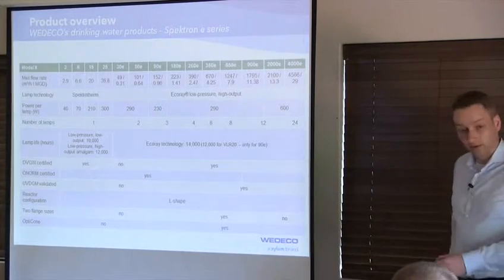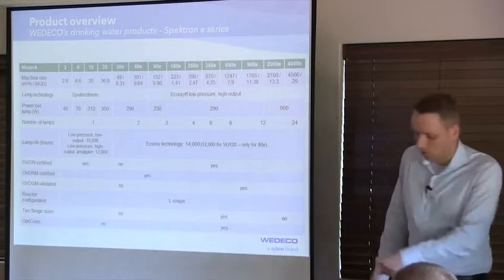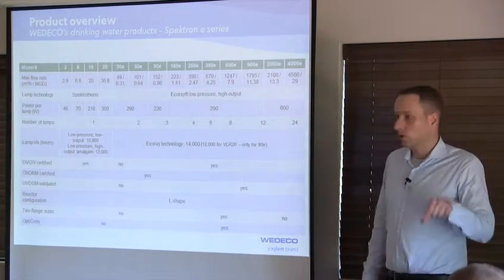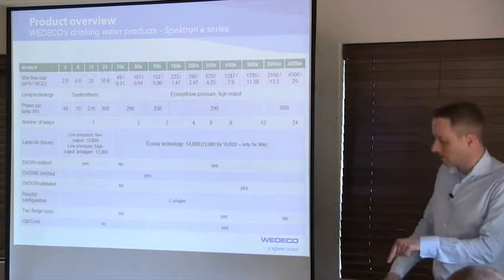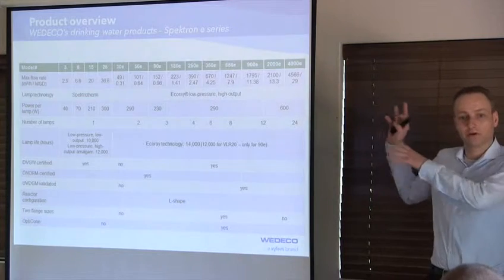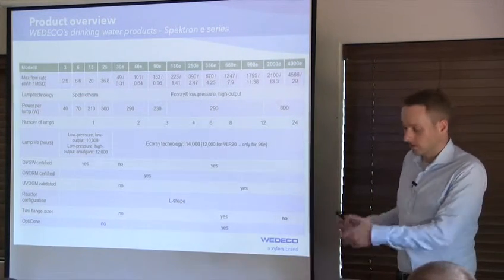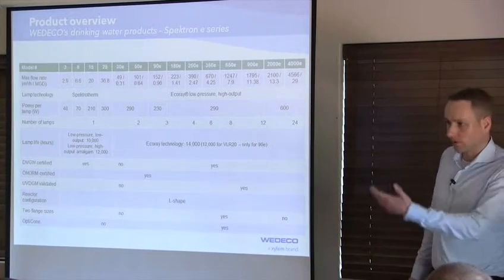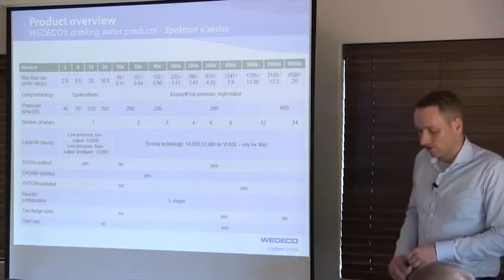It gives you a lot of safety, and it gives you a lot of confidence that you can say, okay, I know this system, as it has been tested with these parameters, will definitely bring this performance, and I need this system. I don't need to oversize the system to have security because I'm not sure what my system can actually do. Which is the case if you don't have a bioassay, then you're just basically guessing, because 30 millijoules, for example, is just an arbitrary number.